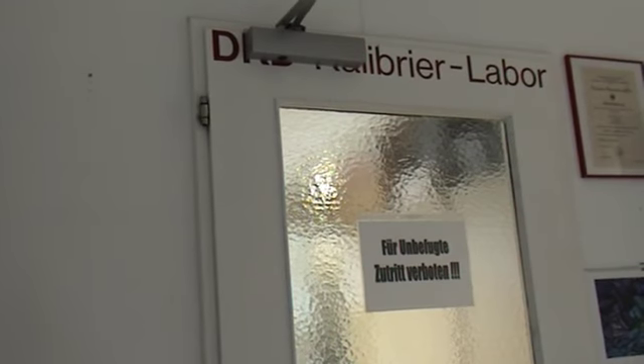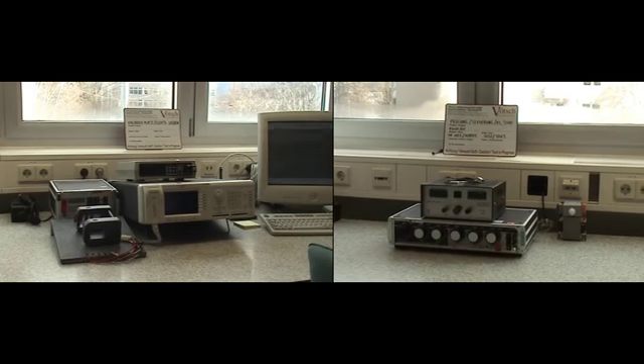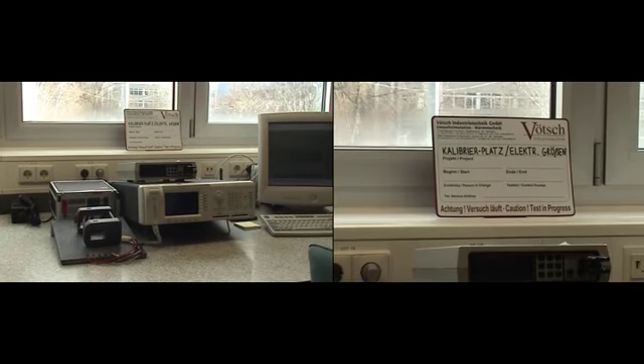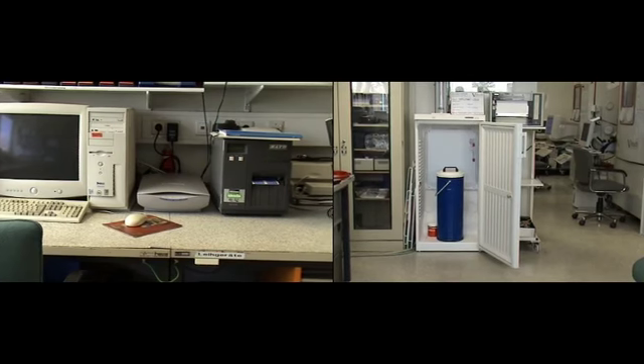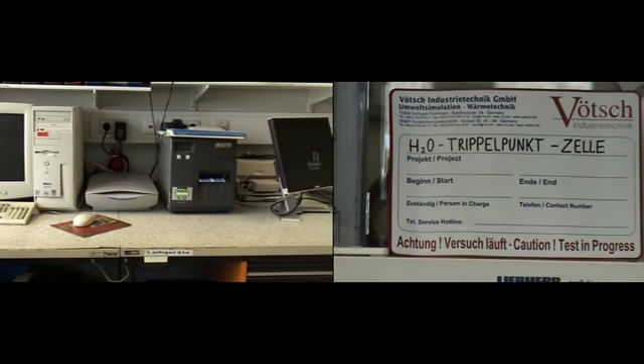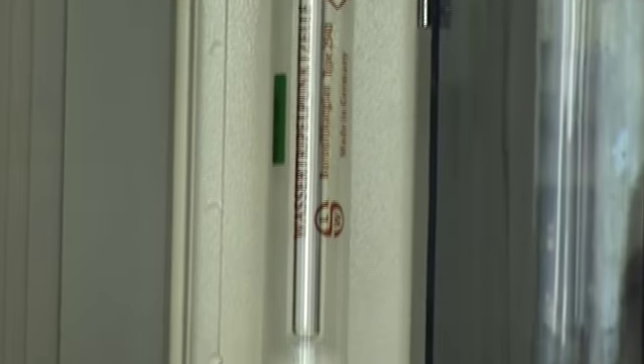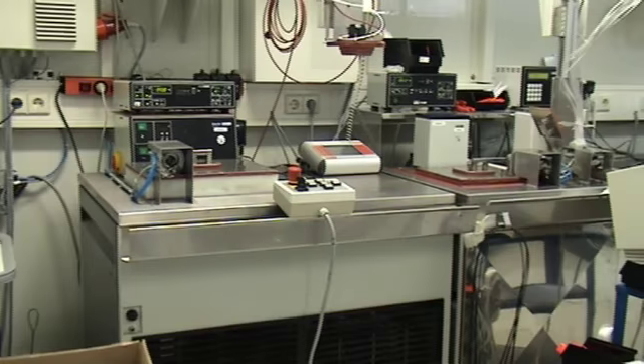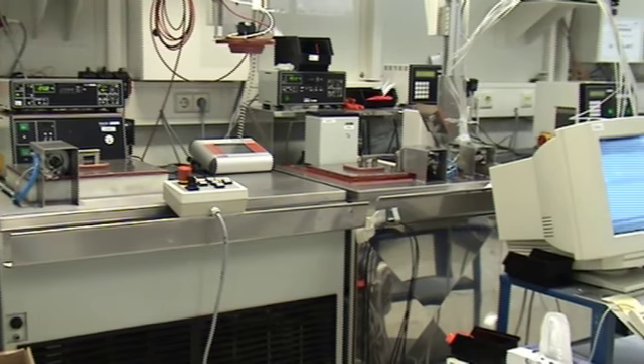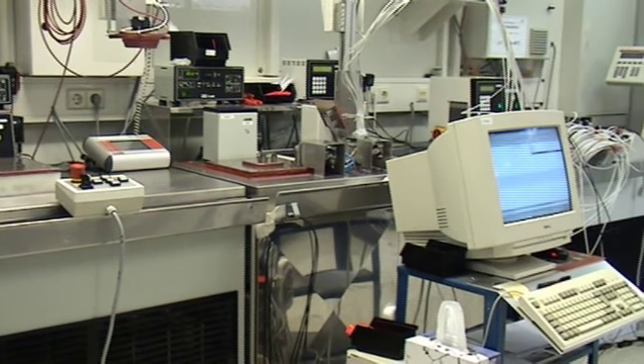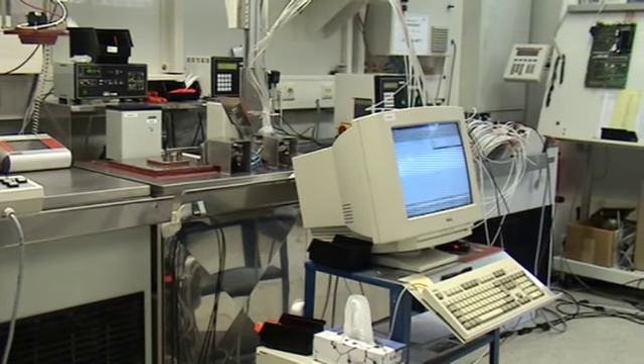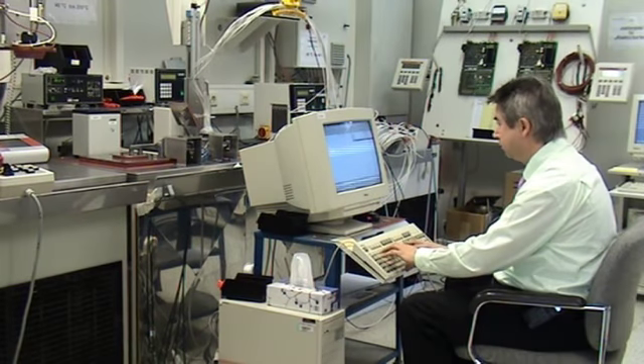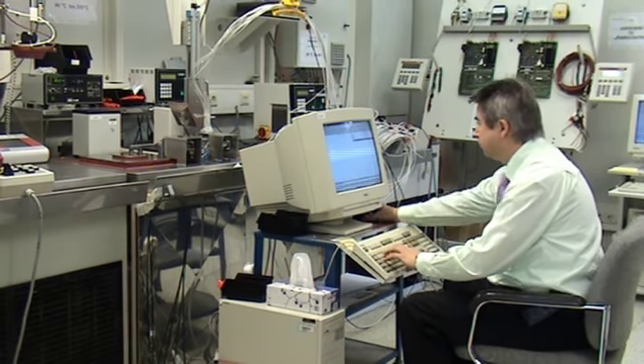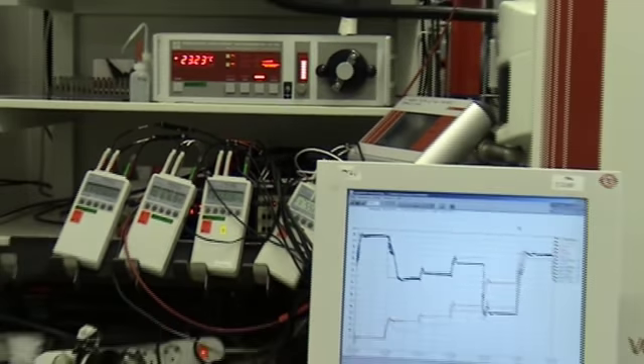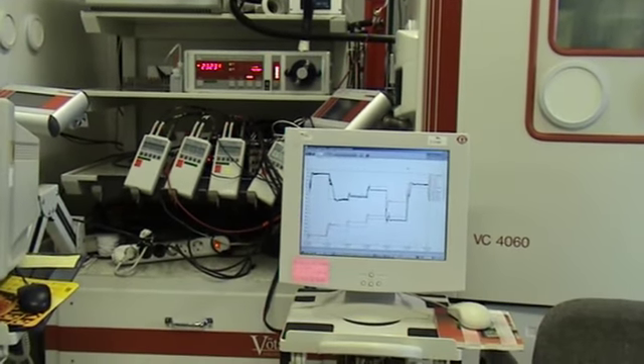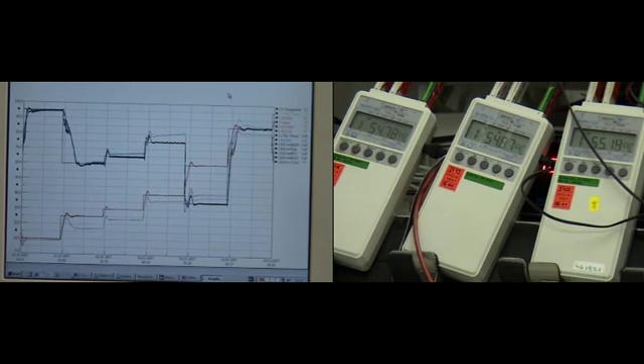Factory calibration certificates are issued by the Vötsch in-house DKD certified calibration lab, providing the confidence and security of receiving a perfectly calibrated chamber. Accredited by the German DKD calibration authorities, Vötsch can issue internationally accepted calibration certificates. A worry-free package for customers that require such certificates.